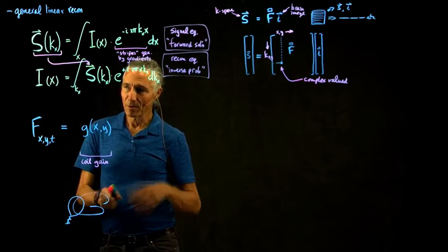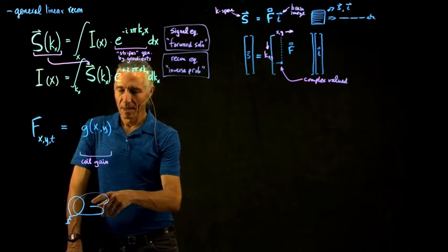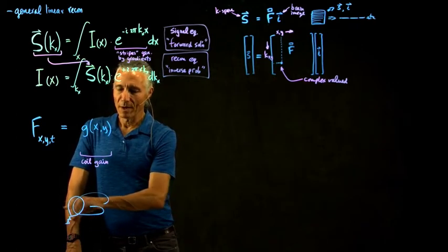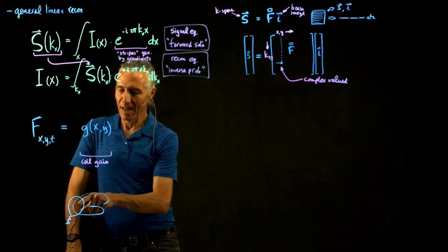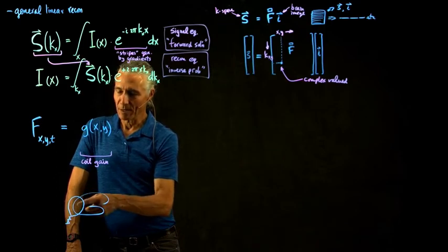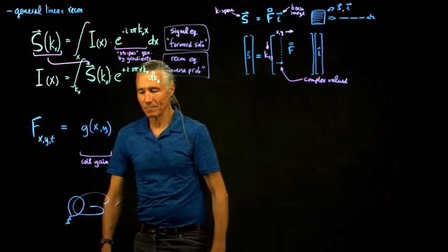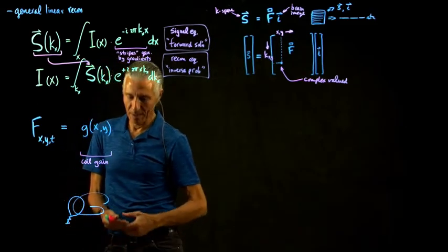But what you could do is take a quick and dirty image through the body coil, and that one would not have any fall off dependent on the coil. Then you take another image from the local coil and look at the ratio between them and figure out how this thing is modifying the signal. And so that's one piece of information.